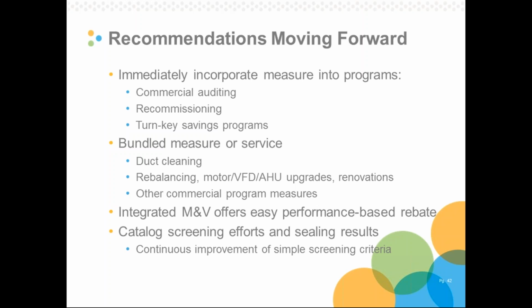Part of that might be due to the risk. We should acknowledge there is some risk because we don't know leakage ahead of time, and we can alleviate that through bundling. Again, I've mentioned this already, but the integrated M&V on this Aeroseal in particular is an extreme advantage, and it makes it easy to do performance-based rebates. I didn't touch on it here, but we put the Aeroseal rig through a calibrated fan flow facility, and we found that it essentially matches our research grade equipment within 2-3% on most of the important flow regimes. And I will acknowledge that our project is limited here in scope.